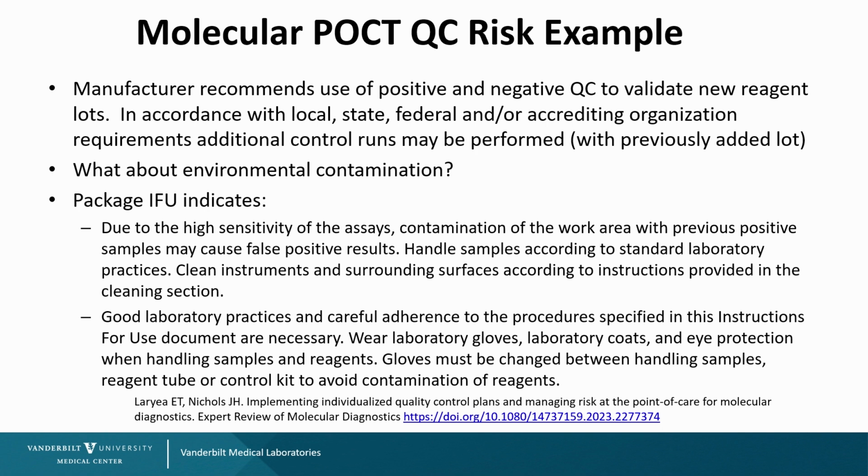And in addition, we put in environmental control, implemented basically taking viral transport media, taking a blank swab and, after we wetted that swab, swabbing the surfaces of the counters, the door handle of the room they were using, the keyboard of the instrument itself, the lid. And if we got a positive, we knew they were contaminating the environment. Our recommendations in the policy were to change gloves between samples, only handle one sample at a time, clean all of the surfaces after each sample, just to ensure that they weren't getting carryover.